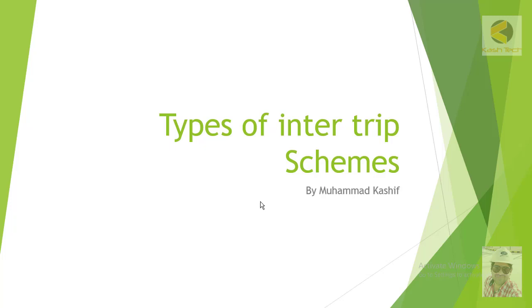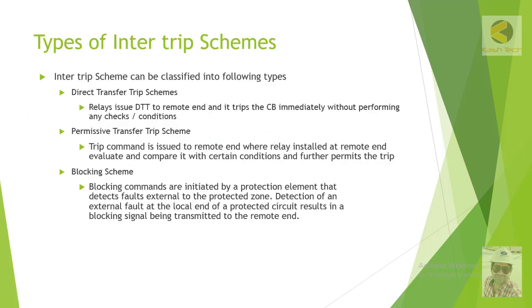Welcome friends. In this section we will study the details and types of intertrip schemes. Intertrip schemes can be classified into the following types. The first is the Direct Transfer Trip scheme, in which the relay issues a direct transfer trip command to the remote end, and it trips the circuit breaker immediately without performing any checks or conditions.